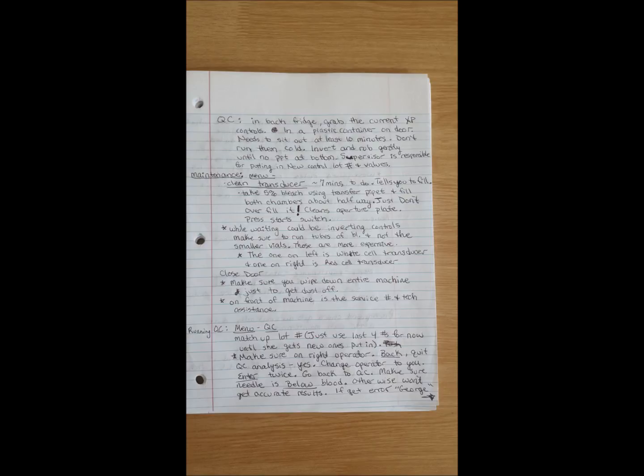After each maintenance, it's going to do an auto rinse and an automatic background check. If it doesn't do a background check, how do you think we do a background check? Come over, push the button, let it run nothing. We want to make sure that our background check has no more than 0.3 whites, no more than 0.02 reds, 0.1 hemoglobin, and 10 platelets. When you're counting nothing, you shouldn't be counting anything. Shouldn't be anything in there.